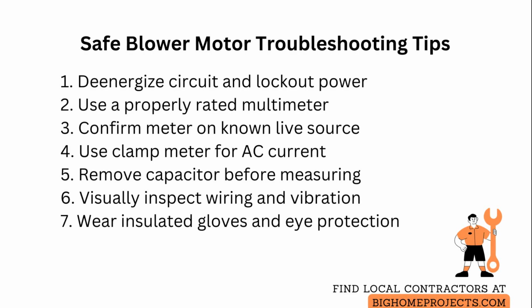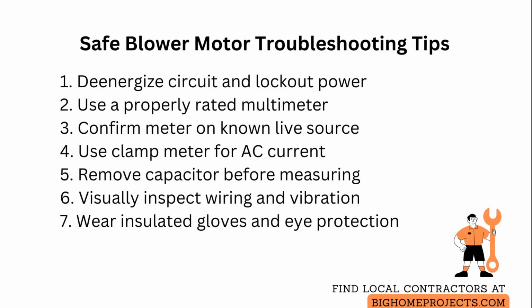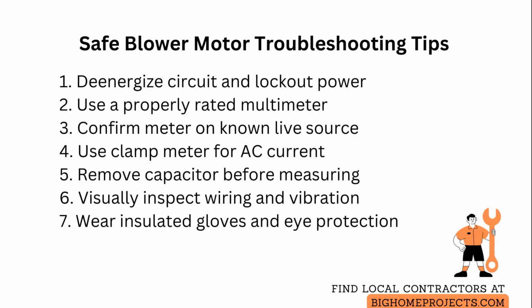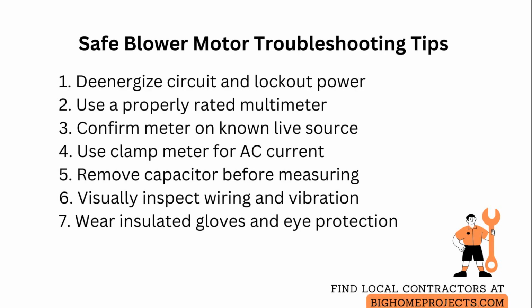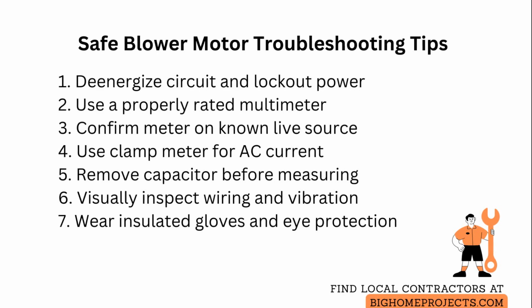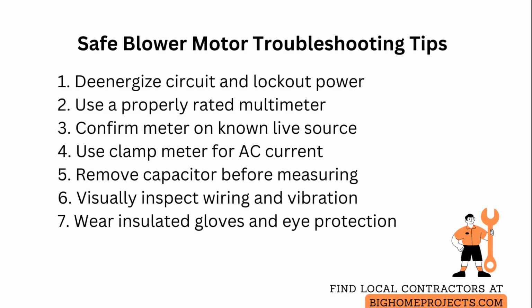When testing capacitors, measure them with the circuit fully discharged and the capacitor removed if possible, because an in-circuit reading can hide faults and a charged capacitor can deliver a dangerous shock. Use visual inspection for loose wiring, burnt insulation, oil leaks, or abnormal vibration as a complementary step, but remember these signs do not replace electrical measurements.